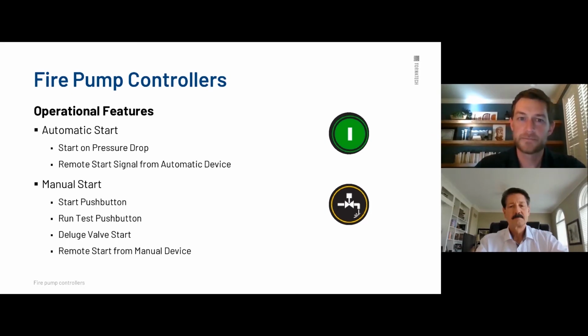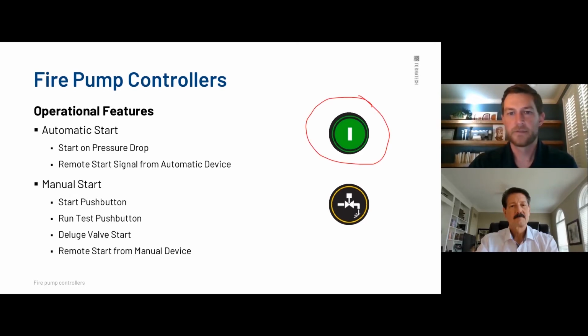But from the factory, most of the time, it's going to be automatic starting and a manual stop. You can have that with a remote start signal from an automatic device or just from a pressure drop, which, again, is the majority of the systems. It's just going to be that pressure transducer that Marty showed in the pressure block earlier on. The other option is manual start, which is going to be this green button here. They all have a green button. That's the manual start button.